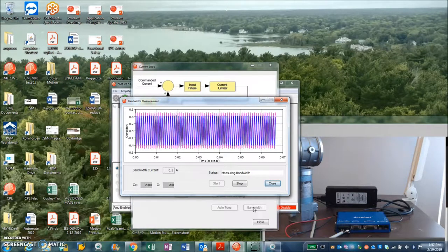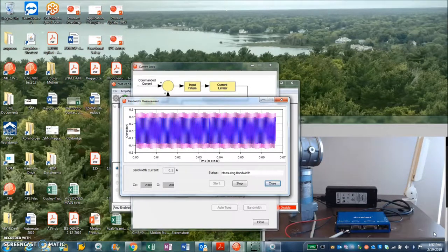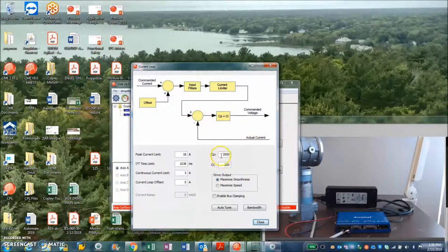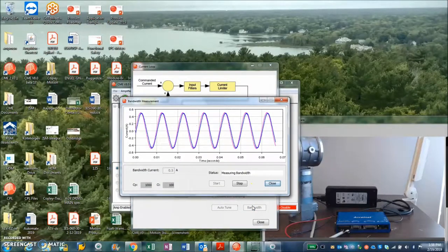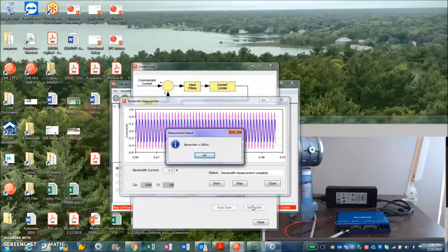What I did notice with the wrong inertia in there, the velocity loop broke into oscillations. So the right value of inertia helps the math model calculate the initial tuning parameters. That's a little excessive, so I'm just going to knock it back down again. So for a DC brush motor, maybe 500 hertz would be sufficient.